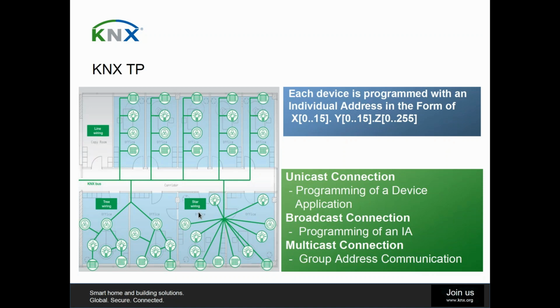In the broadcast, we have normally just like if you want to program the individual address of the device, you put on your program button, and then it will be a red light on it, and you will see that there is a possibility of downloading to one single device. Every device will hear this broadcast, but only that device which is in the programming mode will answer. But in general, this is a broadcast, everyone will hear you.